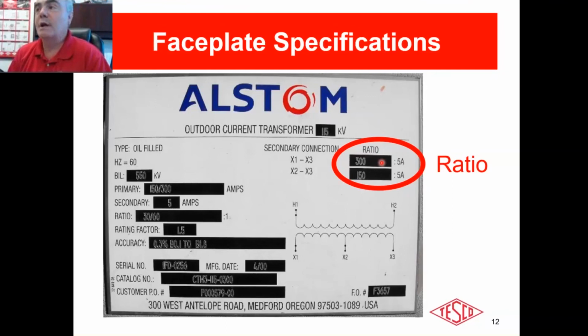On the other hand, we also had a customer who discovered several years later that they had underbilled the customer by 2/3. They had a CT that was wired backwards. In that particular case, they didn't backcharge the customer anything, they apologized profusely, they corrected the service, and within 6 months, the customer and 100 jobs were gone because they could not afford triple the energy bill, because energy was a major component of their manufacturing cost. All right, they were an extruder and they couldn't handle triple the bill. The utility acknowledged it was their issue. Nobody had tampered with the service. It had been that way since the building was built 8 years ago or something like that.